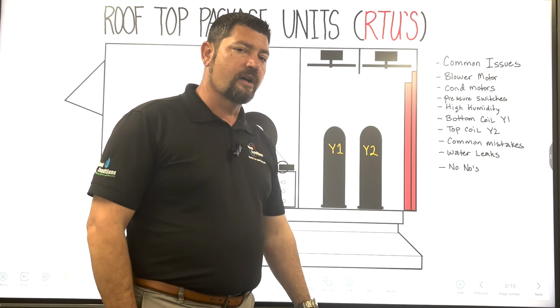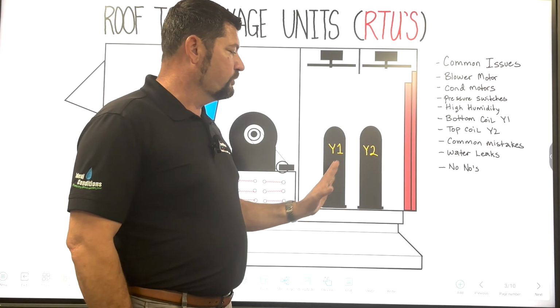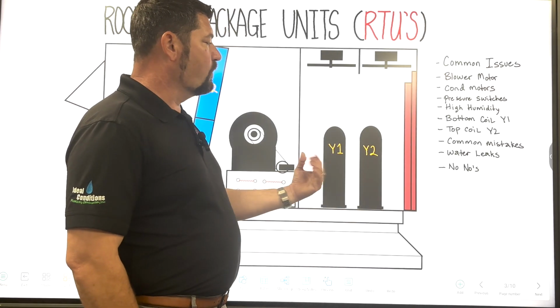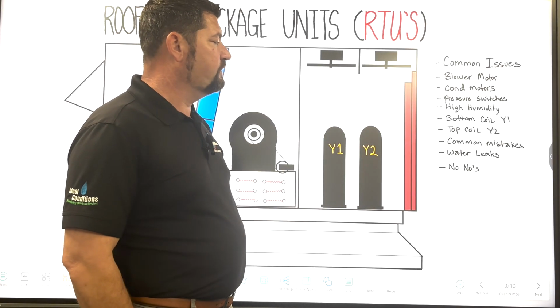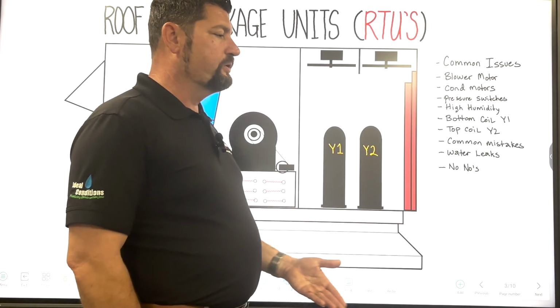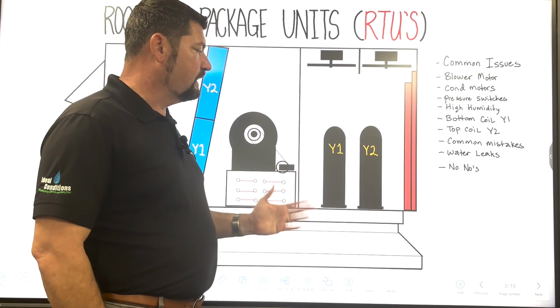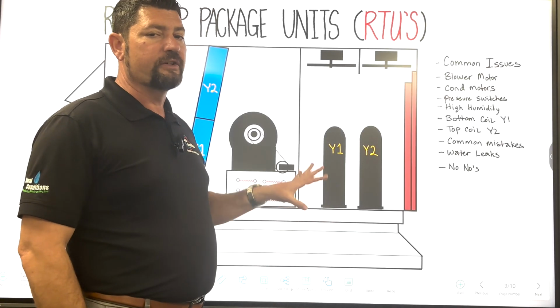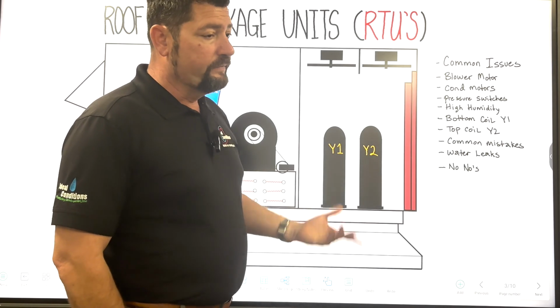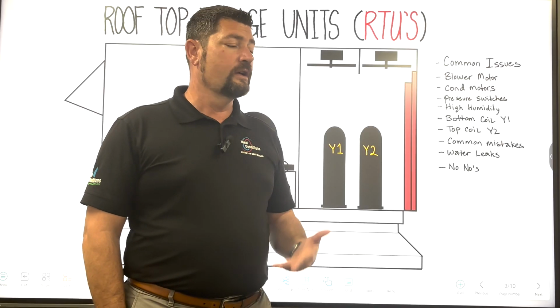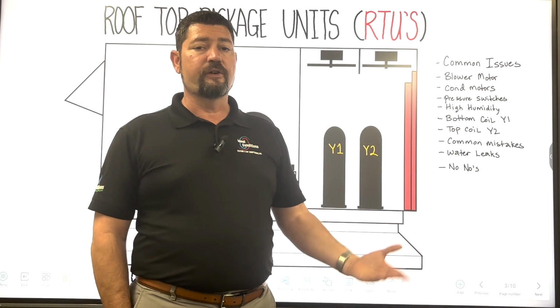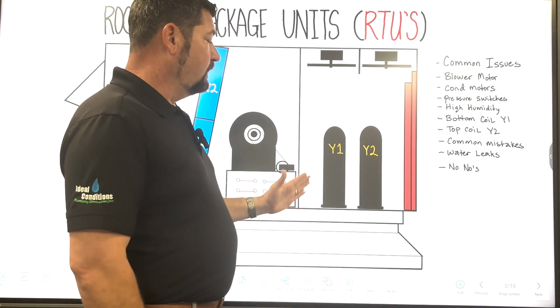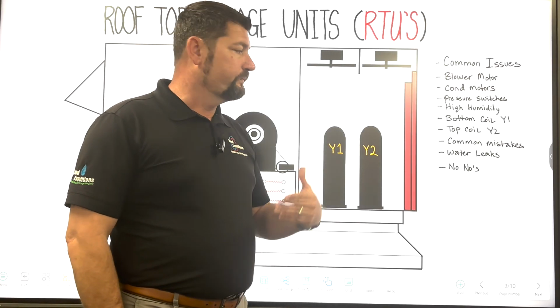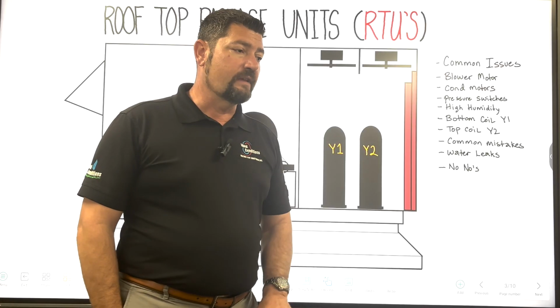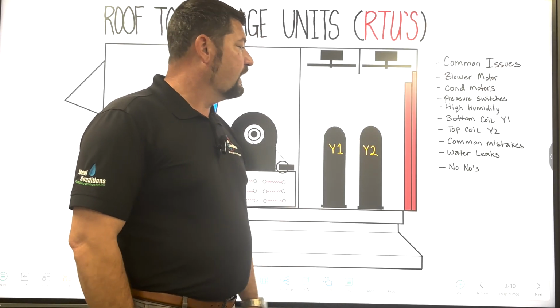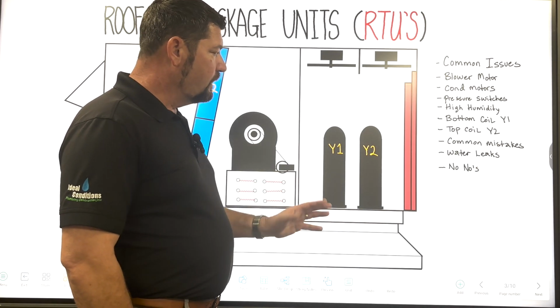These things were built to be on top of a hot roof, and you're not supposed to have to take refrigerant out of them or alter the amount of refrigerant that's required to be in there. If you are working on it, you want to scale that refrigerant back in to make sure it's at factory levels. A lot of technicians are still going off of temperature splits and low side and high side pressures. That's not enough value to get all the information you need to make sure the system's running properly. As a matter of fact, if you think it is, then ask yourself, when the manufacturer rep, the FR, comes out to inspect it, they don't just take these 3 readings. They wind up taking about 13 to 15 values, not to include amp draws and everything else. And they make you fill out all this paperwork, and they want to find out why they even need to come out there, if they need to come out there. And if they do need to come out there, they don't want to do your job. So they'll supervise these machines being worked on by a technician.